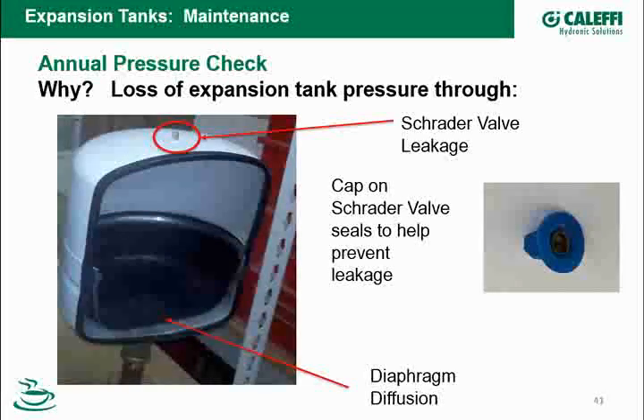Okay. Well, a couple questions then. One in regards to ASME. It's not a question, but we had at least 3 responses of the criteria used for whether or not an ASME tank is needed for an expansion tank. One criteria says that if the total volume of your expansion tank is greater than 119, much like other types of tanks, an ASME rated tank is needed. Another engineer wrote that if your system pressure or your PRV is rated over 30 psi, then that will require the expansion tank to be ASME. And another one just came in that the tank needs to be rated 2.5 times the working pressure of the boiler. I guess that's what they do in Bronco territory. I guess that means Colorado. So there's different regional requirements for ASME, I guess. So your point's well taken. It's whatever the engineer understands is the needs in his marketplace.